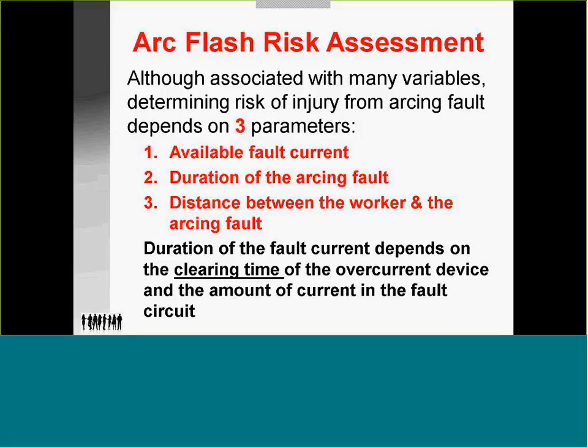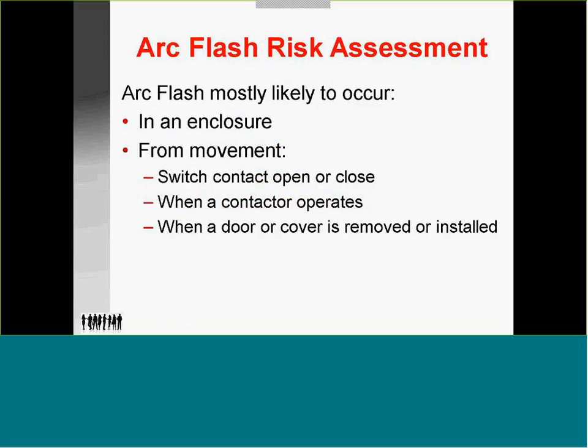Distance between the worker and the arcing fault. The energy level lowers quickly with distance. The fault current depends on the clearing time of the overcurrent device and the amount of current in the fault circuit. Arcs are likely to occur inside an enclosure from the switch contacts opening and closing. With a contactor, this would be control voltage, 120, that's working relays for the higher voltage.